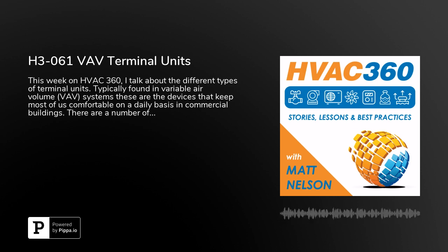When you deal with ceilings, and I've talked about this on maintenance access, realize how far above the ceiling you're putting these things. You should be able to reach them with a ladder without deconstructing the ceiling. And if you locate a VAV box above a hard ceiling, shame on you. You should cross-check your VAV boxes with the reflected ceiling plan that you were supplied by the architects.